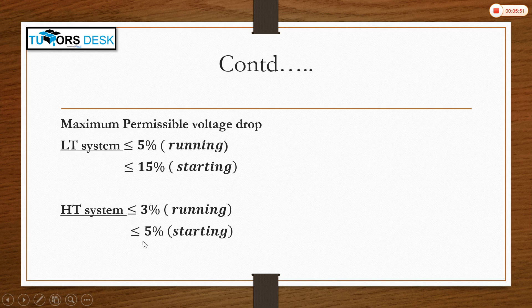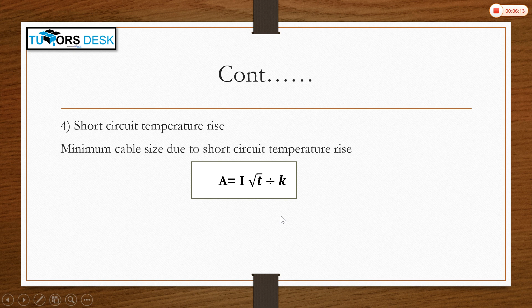The fourth step for selecting the cable is short circuit temperature rise, which is given by A equals I root T divided by K, where A is the cross-sectional area of the conductor, I is the fault current in kiloamperes, and T is the duration of fault current in seconds. That is based on the protective device we are using.